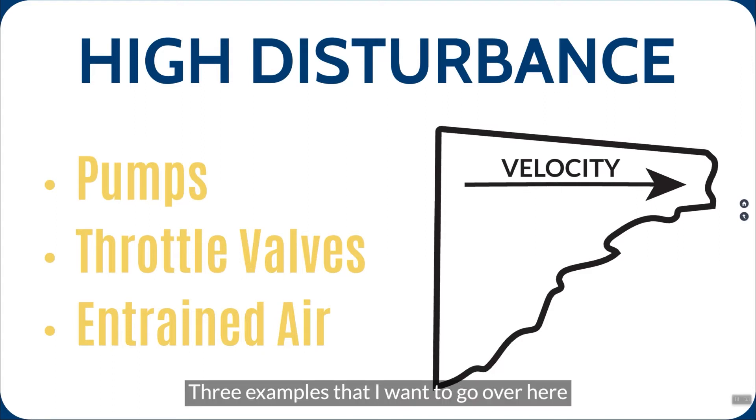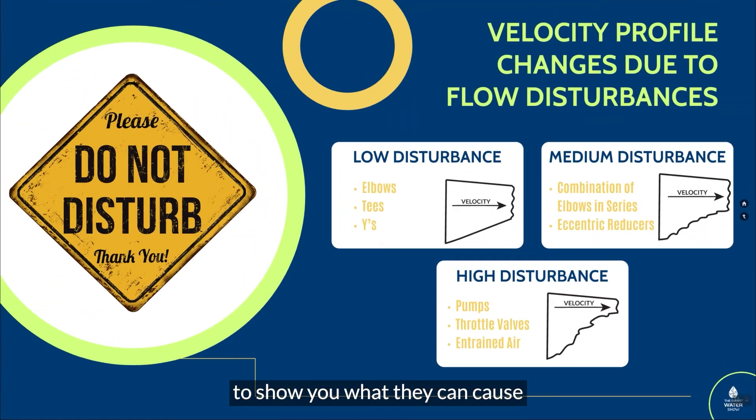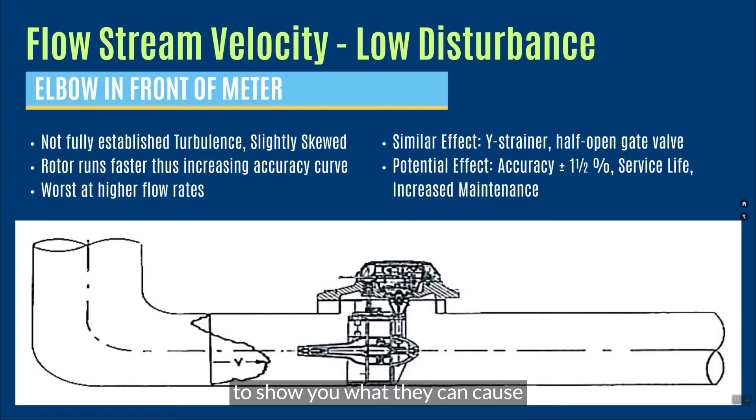Three examples that I want to go over here to show you what they can cause when you have an installation that's not done correctly. In this case, let's say I've got an elbow in front of the meter. All manufacturers give you the amount of straight pipe that they want before the turbine element. And the reason they do this is because the straight pipe in front of the turbine element will straighten out that velocity profile.